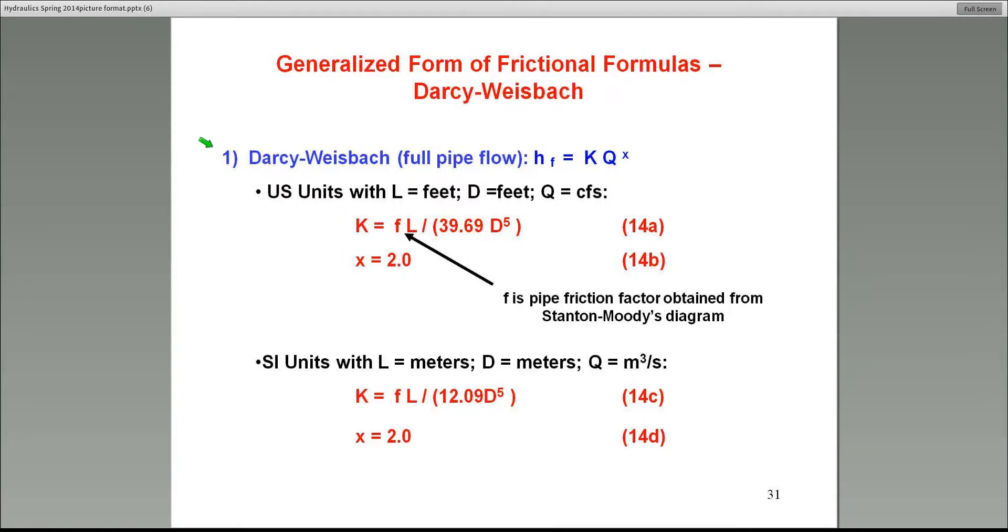The first one is for Darcy-Weisbach equation. I will not emphasize that equation too much here, but nonetheless, you should know when you go to solve some problems how to use this equation. This is head loss equal to K, Q to the power of x again, where x is 2.0. And here's the K value. f, as you all know, is the friction factor in the pipe, typically obtained from Stanton-Moody's diagram.